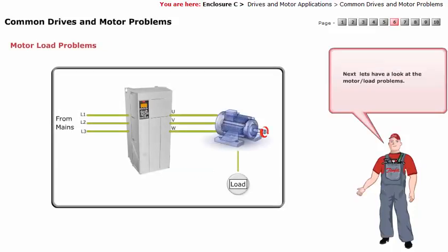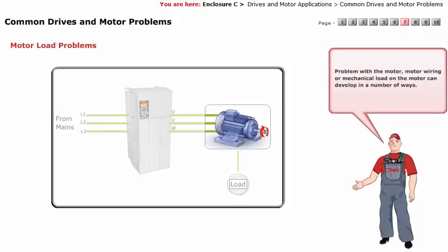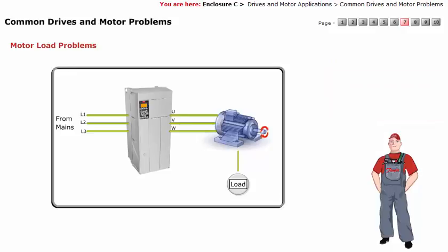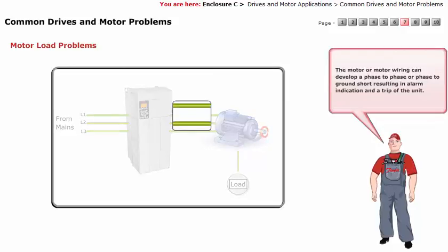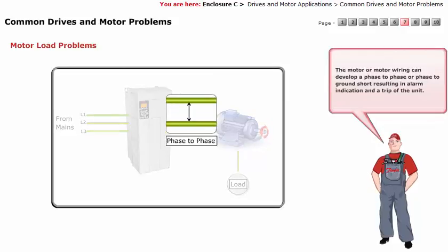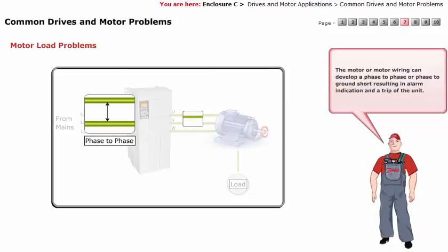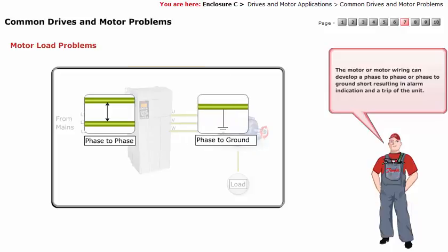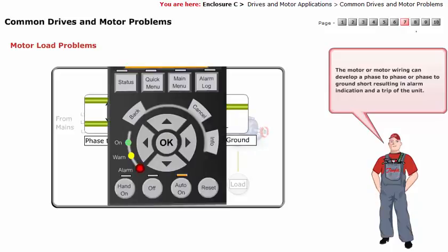Next, let's have a look at the motor load problems. Problems with the motor, motor wiring, or mechanical load on the motor can develop in a number of ways. The motor or motor wiring can develop a phase-to-phase or phase-to-ground short, resulting in an alarm indication and a trip of the unit.